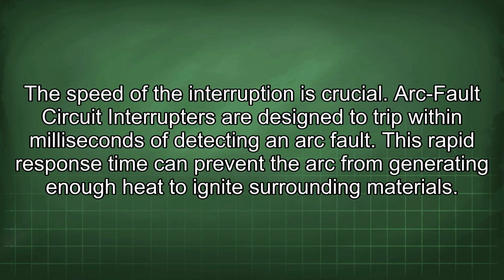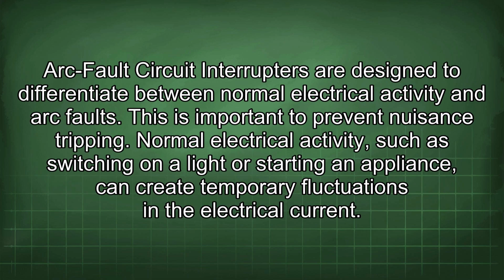The speed of the interruption is crucial. Arc fault circuit interrupters are designed to trip within milliseconds of detecting an arc fault. This rapid response time can prevent the arc from generating enough heat to ignite surrounding materials. Arc fault circuit interrupters are designed to differentiate between normal electrical activity and arc faults. This is important to prevent nuisance tripping.